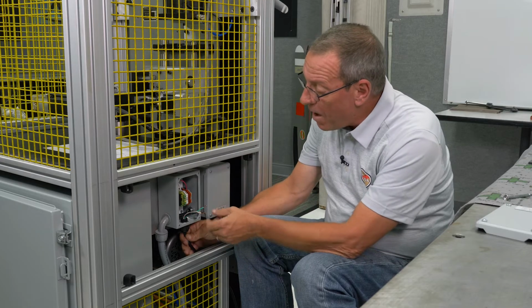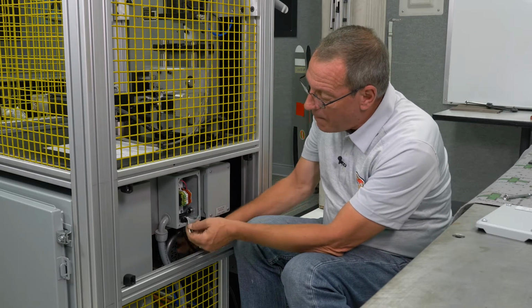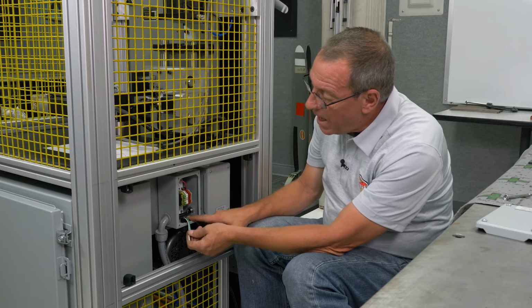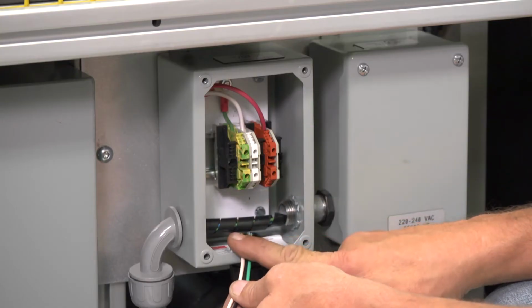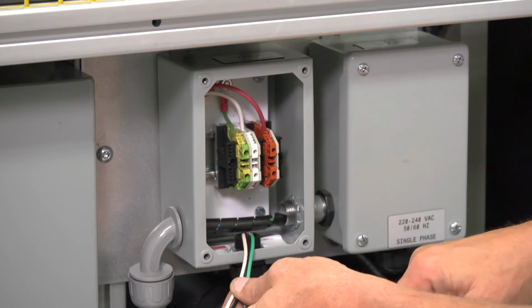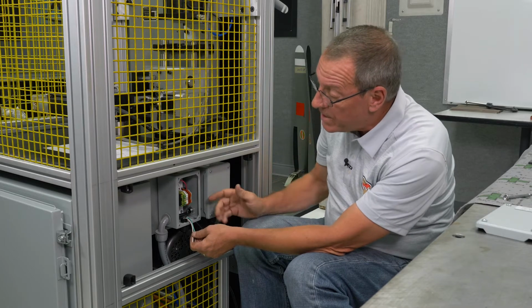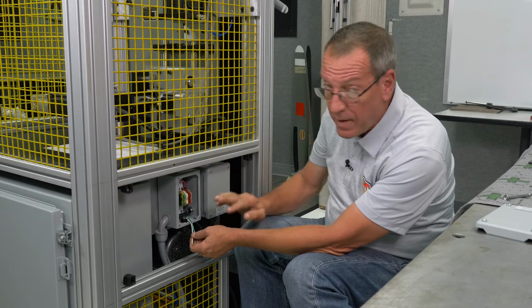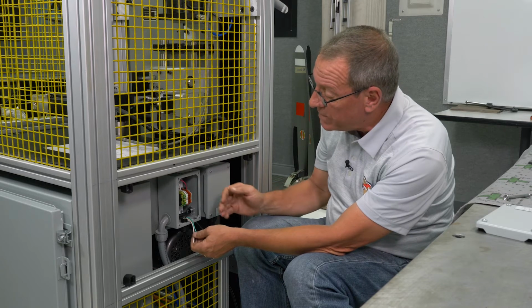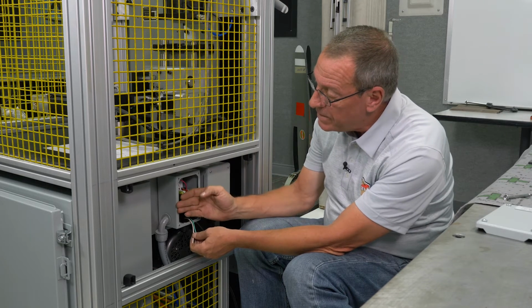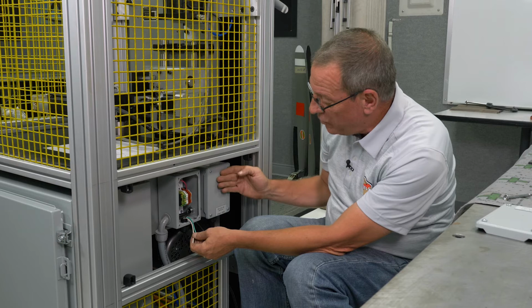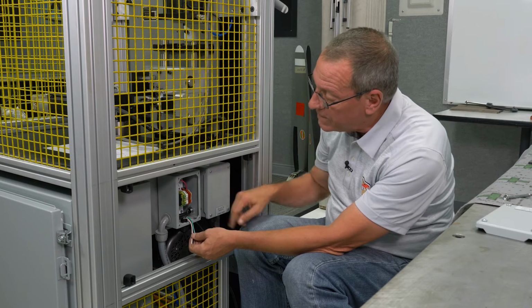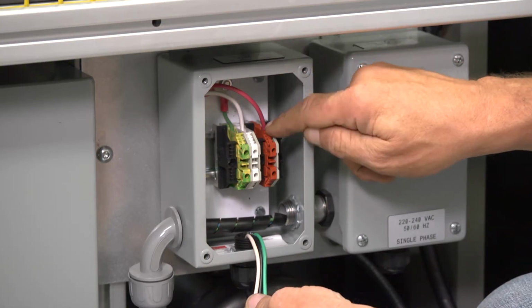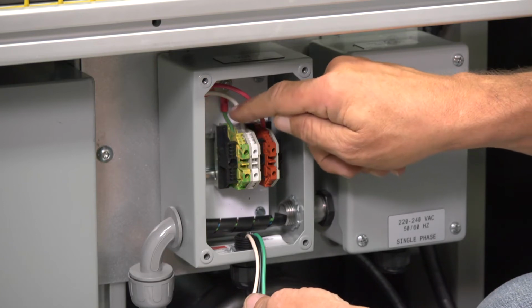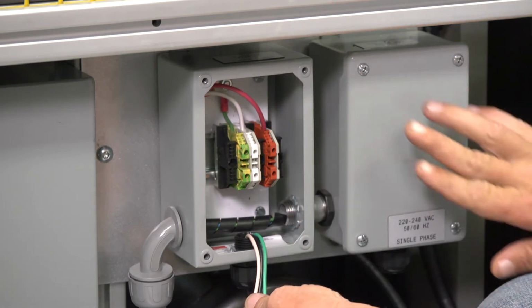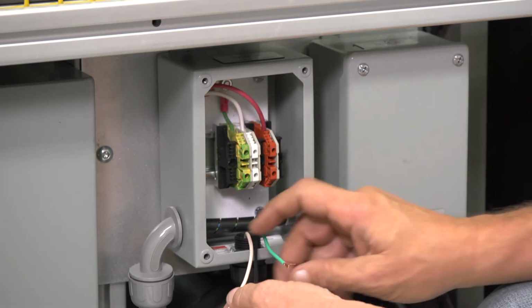So I've pulled my power cord up through the grommet on the bottom of the box, and I'm ready to wire the power cord to the terminals. No matter which set of boxes you're working with, it's the same in both sides, either the 110 to 127 or the 220 to 240 box. You've got supply, common, and ground. They're in the same locations, just in another box.